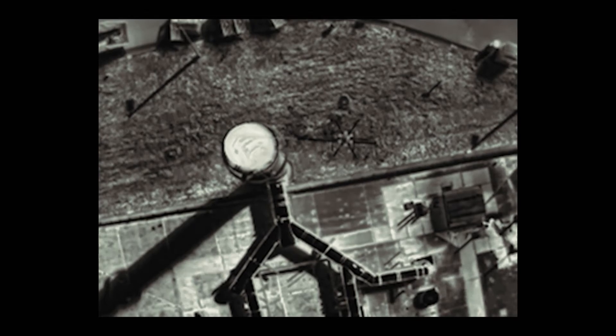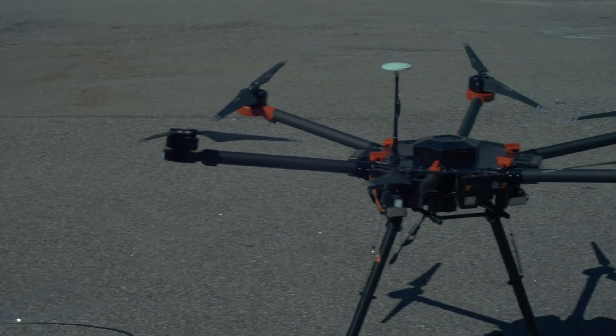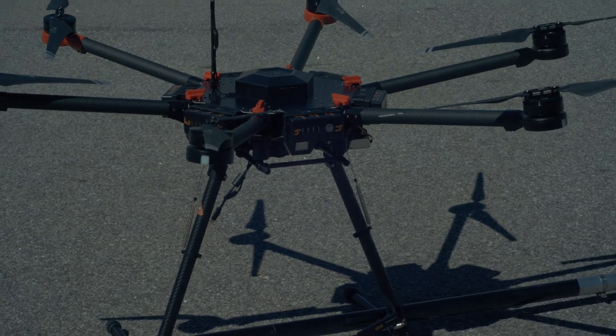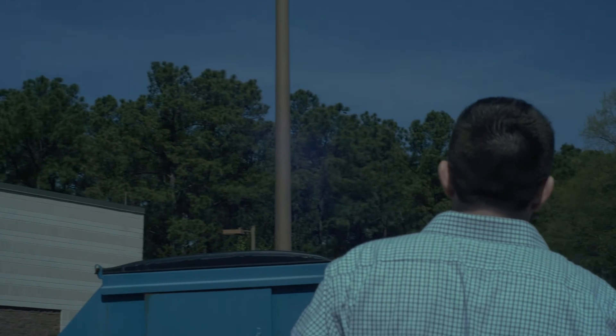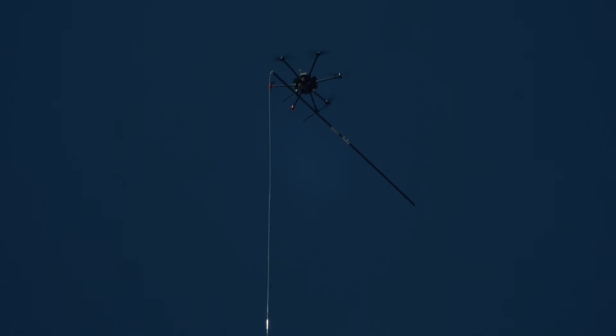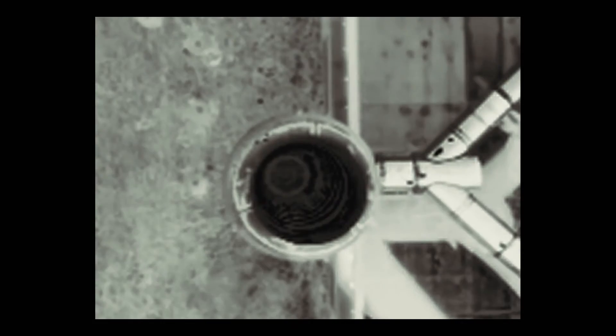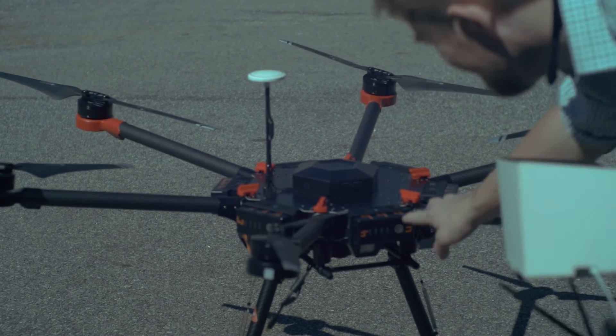We were very excited about the results because within just 20 minutes we were able to acquire a sample from a 120-foot stack. In my previous work I've done quite a bit of sampling on utility boiler stacks, and I know from experience it would have taken half a day to acquire that sample using traditional techniques — sending a stack testing crew up a stack, setting up equipment, acquiring the sample. We were able to do that work in only 20 minutes. When the scope of the work is to go out and sample hundreds of sources within an eight-day period, we think this technology definitely fits in well.